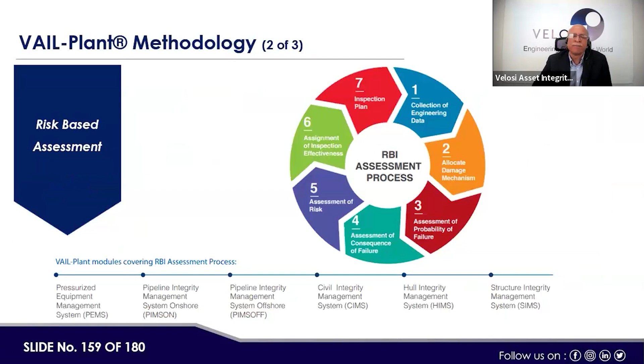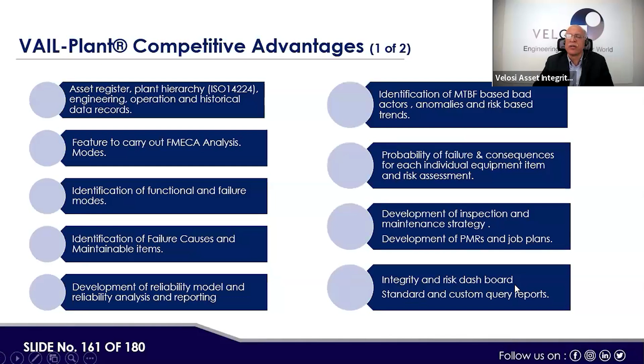Under this system, we develop an asset register in accordance with ISO 14224, carry out FMECA analysis for the CP system, identify functional and failure modes, identify failure causes and maintainable items, develop a reliability model and reliability analysis and reporting, identify MTBF-based bad actors, anomalies and risk-based trends. Then we calculate probability of failure and consequence of failure for individual equipment or tags, develop inspection and maintenance strategy, develop PMR and job plans for the CP system, and include an integrity and risk dashboard, standard and custom query reports as part of the system.